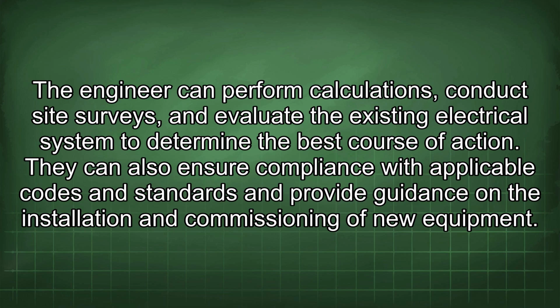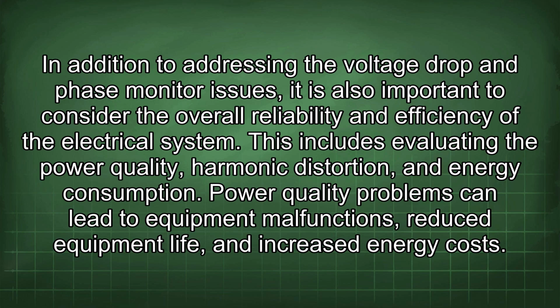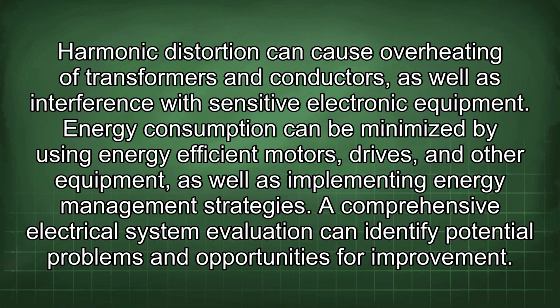In addition to addressing the voltage drop and phase monitor issues, it is also important to consider the overall reliability and efficiency of the electrical system. This includes evaluating the power quality, harmonic distortion, and energy consumption. Power quality problems can lead to equipment malfunctions, reduced equipment life, and increased energy costs. Harmonic distortion can cause overheating of transformers and conductors, as well as interference with sensitive electronic equipment. Energy consumption can be minimized by using energy-efficient motors, drives, and other equipment, as well as implementing energy management strategies.